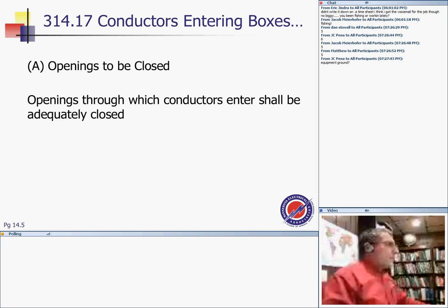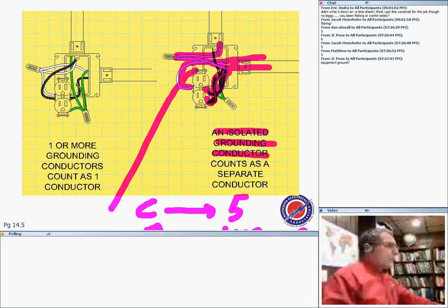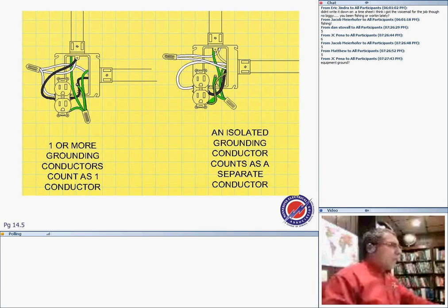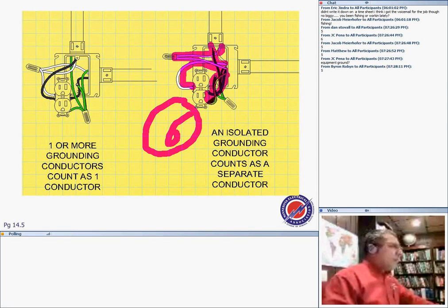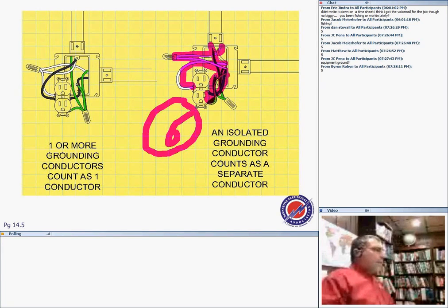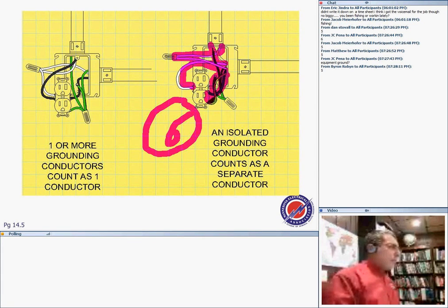Very good point. Equipment grounding conductor. Let's count them one more time, guys. Here's one conductor, the neutral: 1, 2, 3, so 3 conductors for the neutral, right? And here's one for the hot, that's 4. This is ground 5, and ground 6. You're absolutely right, there should be 6. We forgot that you count the ground twice, one for the isolated ground and one for the ground. I forgot that there's an isolated ground here.